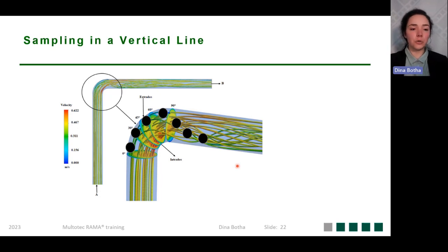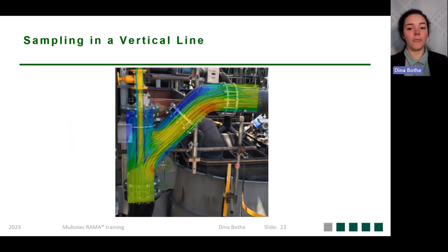So we've learned a rule or two with vertical line sampling. If we do, it is usually for process control purposes. It is on a pumped line, it has vertical upwards flow, and we need to install our sampler usually 2 to 3 pipeline diameters after a bend, a split, or a connection. And that will help with this preferential turbulence.